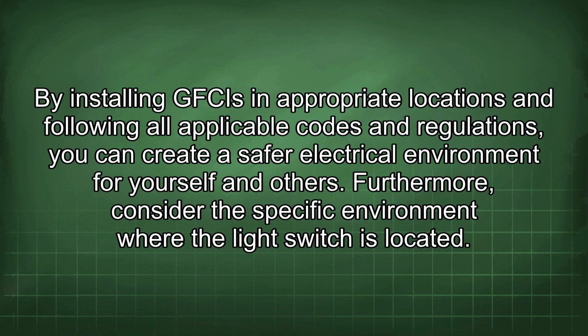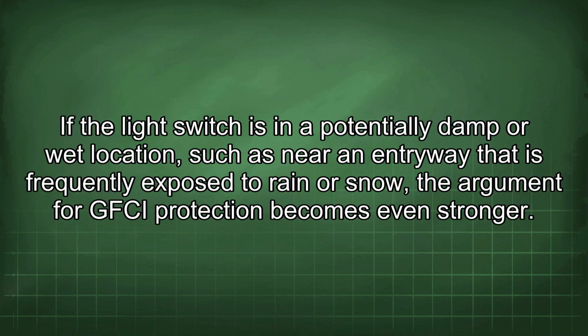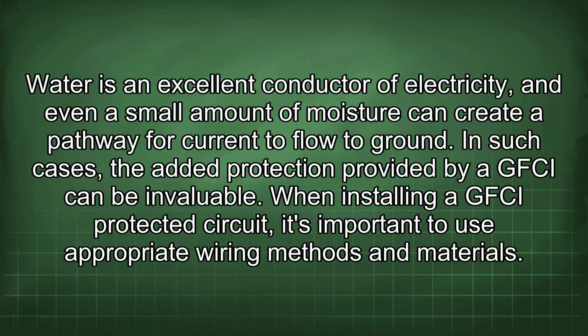By installing GFCIs in appropriate locations and following all applicable codes and regulations, you can create a safer electrical environment for yourself and others. Furthermore, consider the specific environment where the light switch is located. If the light switch is in a potentially damp or wet location, such as near an entryway that is frequently exposed to rain or snow, the argument for GFCI protection becomes even stronger. Water is an excellent conductor of electricity, and even a small amount of moisture can create a pathway for current to flow to ground. In such cases, the added protection provided by a GFCI can be invaluable.